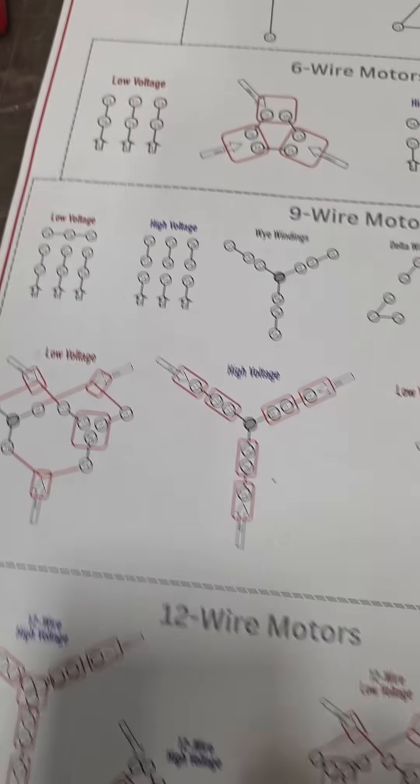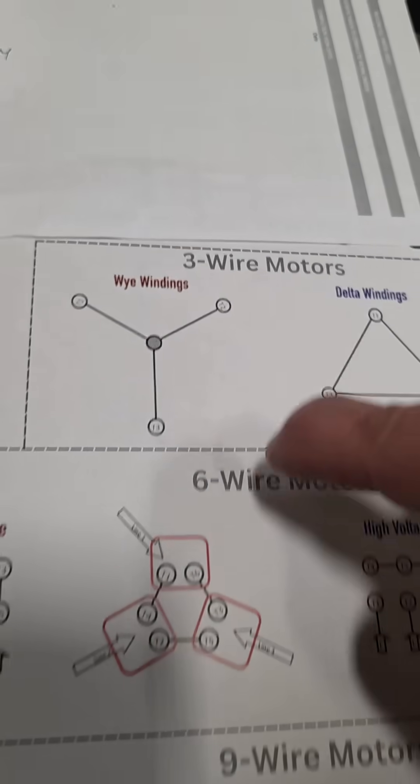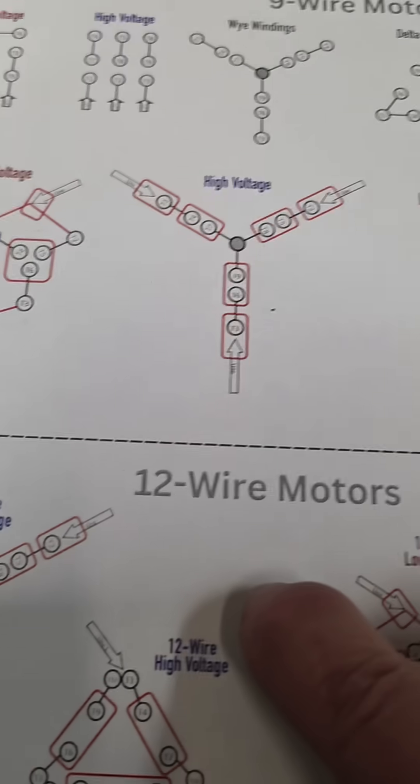And in this case, it's written right here on the motor. These are the instructions on how to wire this bad boy to high and low voltage. All I really had to do was print out this diagram, which shows you how to wire three wire, six wire, nine wire, and 12 wire motor.